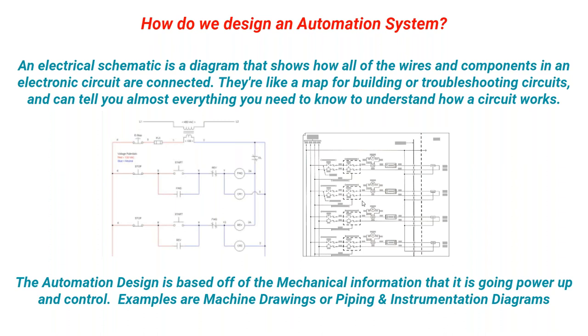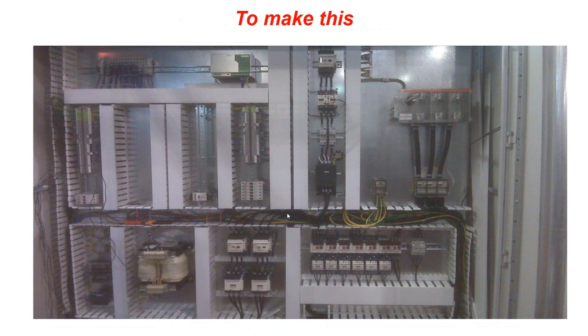So how do we design an automation system? We use an electrical schematic diagram, which shows where all the wires are going and how the circuit works. We use it to help troubleshoot and build. The automation design itself first has to be based on mechanical information — typically we'll start with a piping and instrumentation diagram, or machine drawings, to understand what we need to control. Then we create the electrical controls schematic.